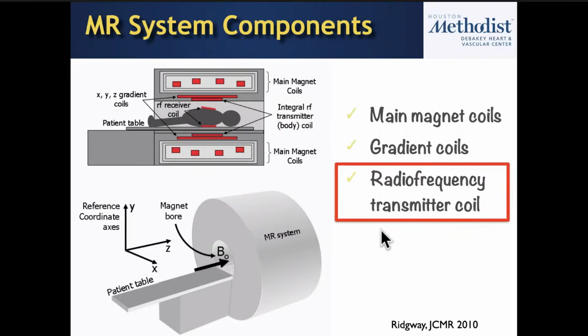So we talked about the main magnetic field, the gradient coils, and then the last thing is the radio frequency coils. There are two sets of radio frequency coils. There's the radio frequency transmitter coils. These are coils that send in a radio frequency pulse. The transmit coils are generally within the scanner itself, although there are some coils that may have transmit capabilities as well.